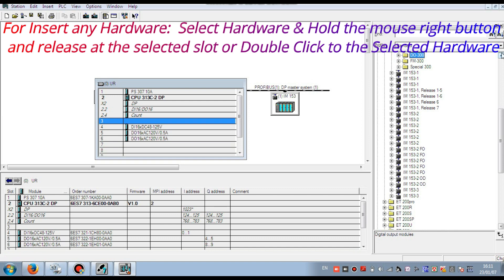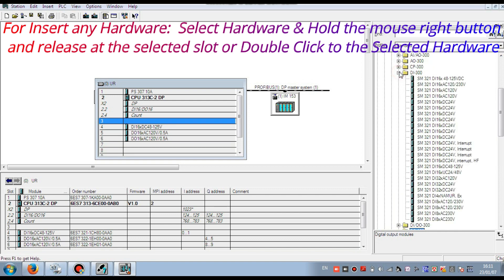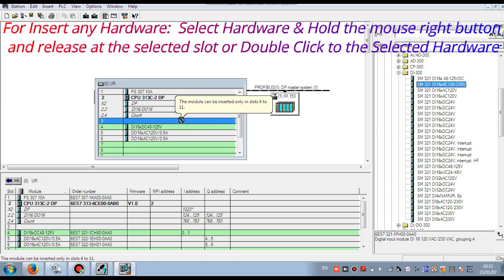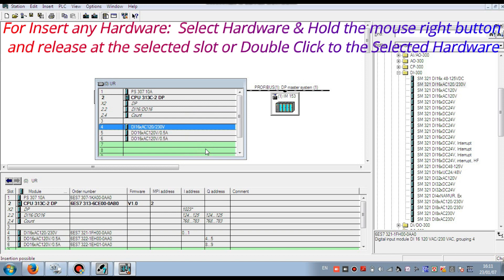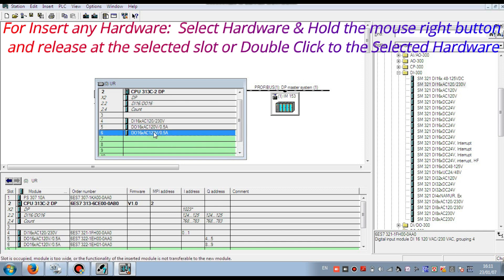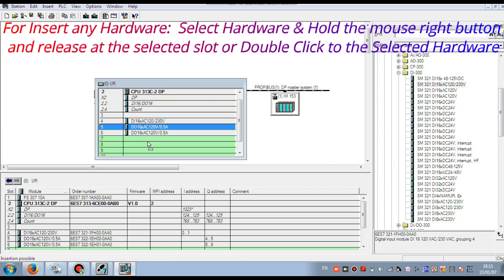But you have to keep in mind: you have to maintain the sequence — digital input first. Here there is a warning because I broke the sequence. I wanted to insert another digital input card, but I had already inserted a digital output card. So the sequence has not been maintained, and it is showing a warning. First I have to empty that slot.